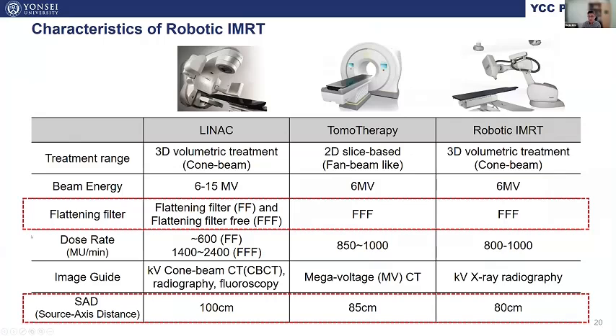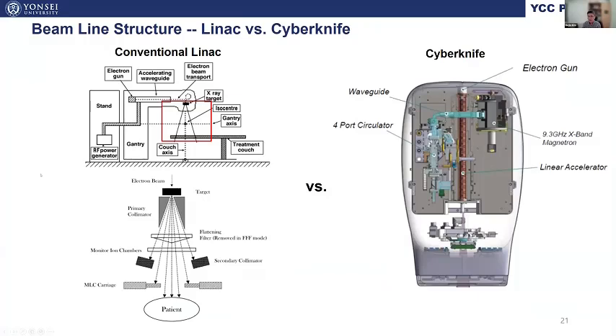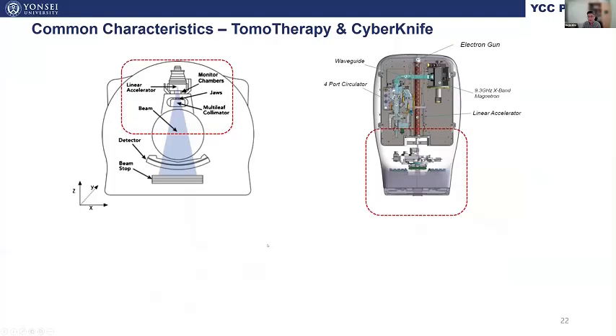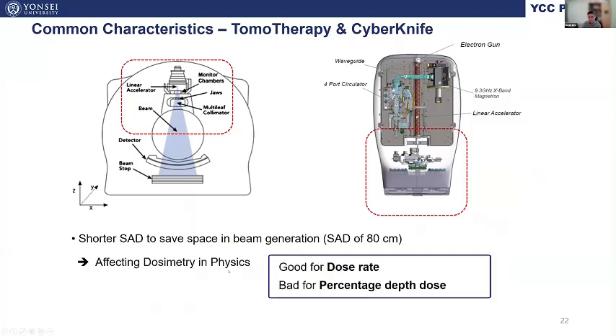Next, CyberKnife shows a unique beam generation structure resulting in different specifications. Unlike conventional LINAC, CyberKnife doesn't have enough space in the beam generation structure, as its linear accelerator is placed at the end of the moving robot. This removed the placement of the flattening filter following the tungsten target and inevitably shortened the SAD to 80 centimeters, which is usually 100 centimeters. This must be good for the dose rate. So CyberKnife has a dose rate of 1000 MU per minute, which is greater than other magnetron-based linear accelerators, while sacrificing the percent depth dose, PDD. This is kind of simple physics. The shorter the SAD, the lower the PDD, due to the inverse square law.